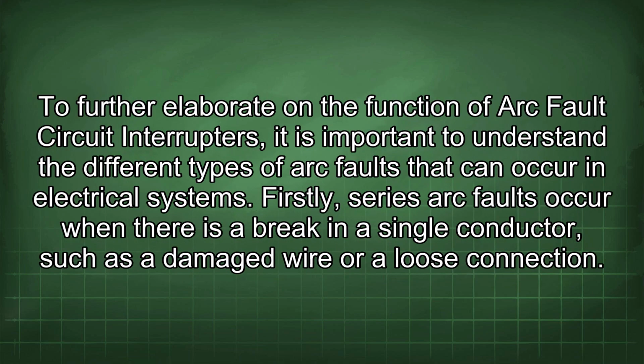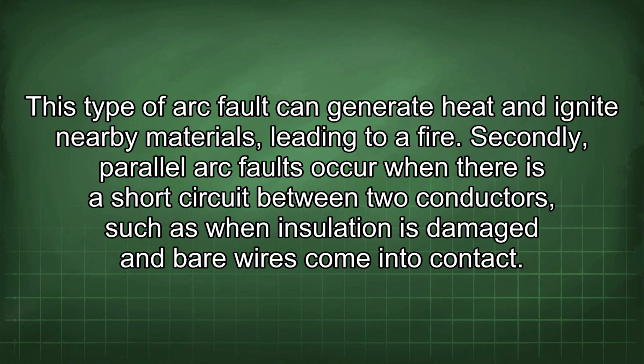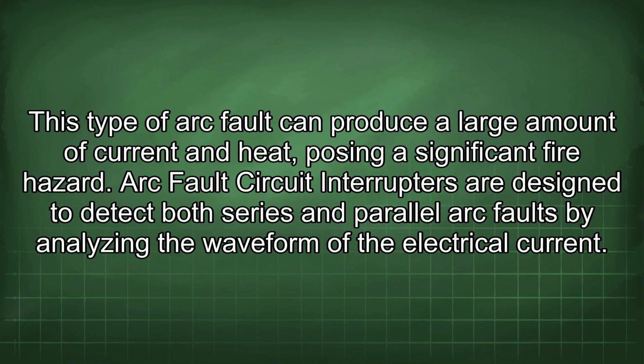To further elaborate on the function of arc fault circuit interrupters, it is important to understand the different types of arc faults that can occur in electrical systems. Firstly, series arc faults occur when there is a break in a single conductor, such as a damaged wire or a loose connection. This type of arc fault can generate heat and ignite nearby materials, leading to a fire. Secondly, parallel arc faults occur when there is a short circuit between two conductors, such as when insulation is damaged and bare wires come into contact. This type of arc fault can produce a large amount of current and heat, posing a significant fire hazard.